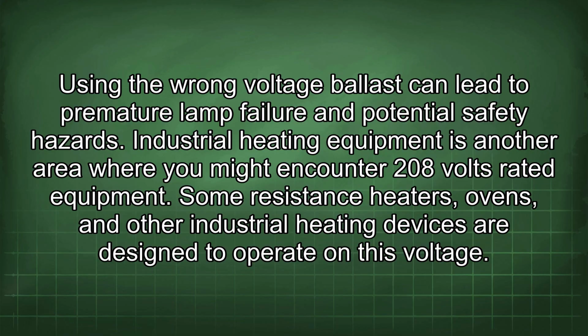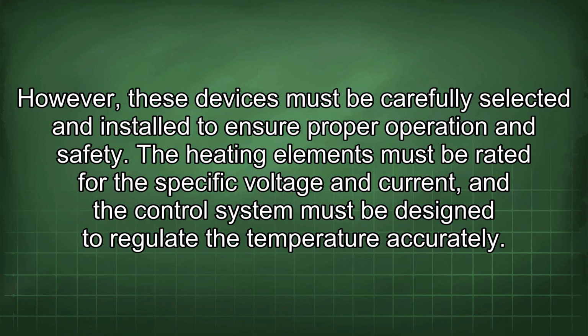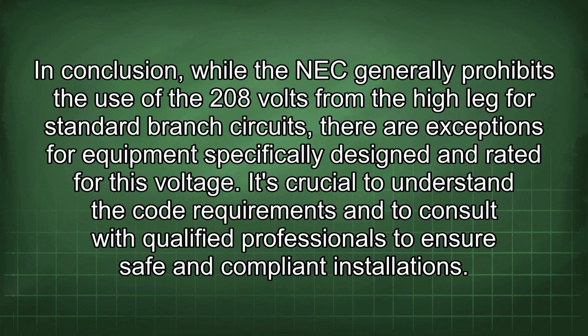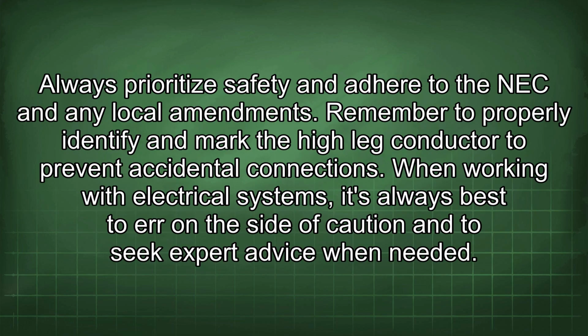Industrial heating equipment is another area where you might encounter 208 volt rated equipment. Some resistance heaters, ovens, and other industrial heating devices are designed to operate on this voltage. However, these devices must be carefully selected and installed to ensure proper operation and safety. The heating elements must be rated for the specific voltage and current, and the control system must be designed to regulate the temperature accurately. In conclusion, while the NEC generally prohibits the use of the 208 volts from the high leg for standard branch circuits, there are exceptions for equipment specifically designed and rated for this voltage. It's crucial to understand the code requirements and to consult with qualified professionals to ensure safe and compliant installations. Always prioritize safety and adhere to the NEC and any local amendments.